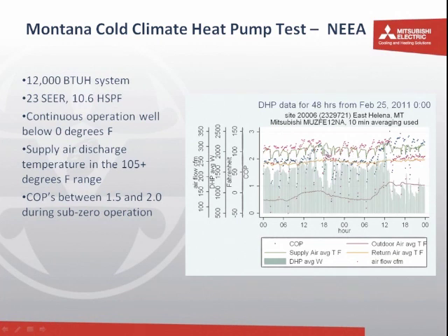The dropouts happen to be when the system goes into a defrost mode, and the fan is actually off during that period. So while the sensor picked up that dip in the temperature, the residents did not actually feel that. The system continues to operate at 100 degrees throughout these extremely cold temperatures. And the coefficient of performance, which is the ratio of energy into the system to energy into the space, continues to be between 1.5 and 2 during this entire extreme low ambient condition.